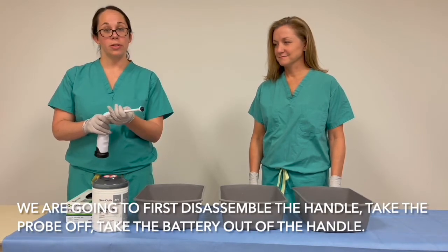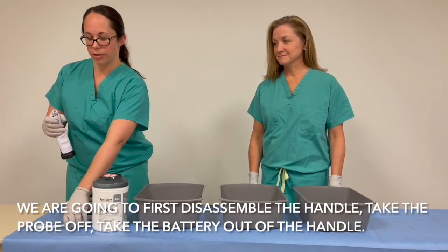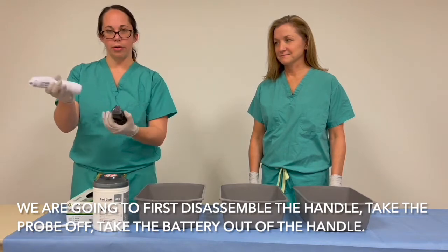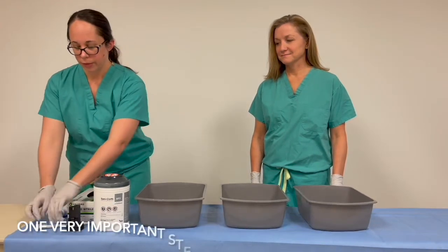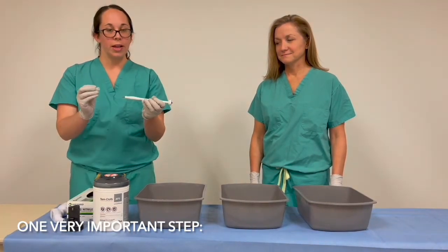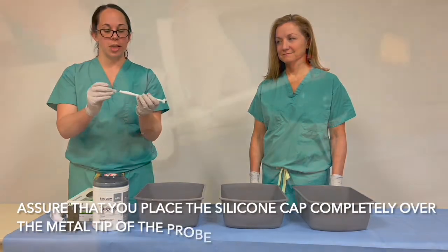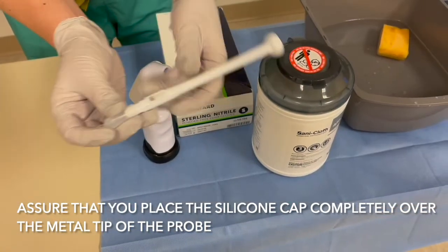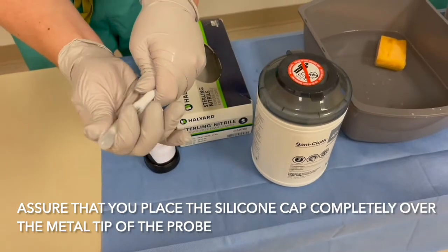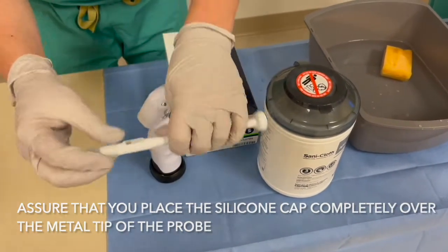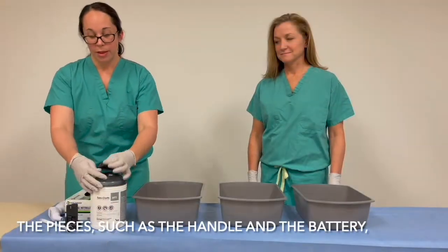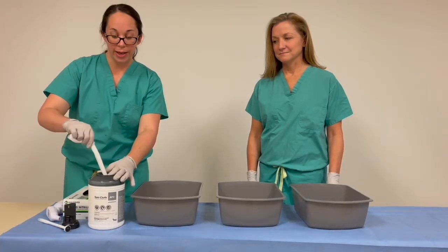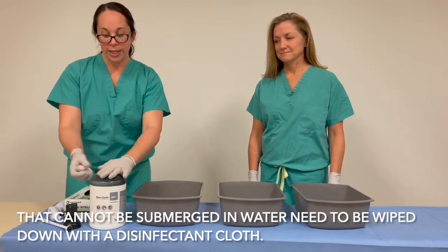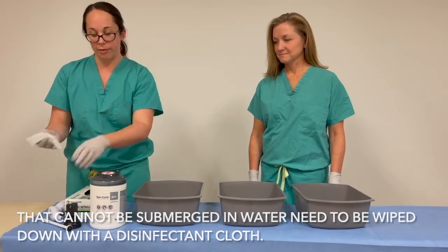We're going to first disassemble the handle, take the probe off, take the battery out of the handle. One very important step, ensure that you place the silicone cap completely over the metal tip of the probe. The pieces, such as the handle and the battery, that cannot be submerged in water need to be wiped down with a disinfectant cloth.